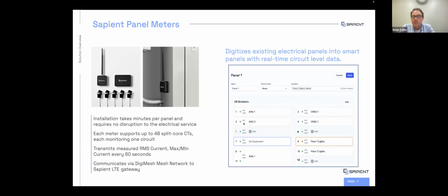We're able to put these on and within minutes have it start communicating back, building a full profile and seeing interesting things, like noting if a VAV is not actually modulating or a drive is left in bypass, on a very instant network.